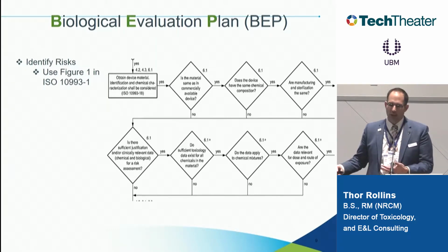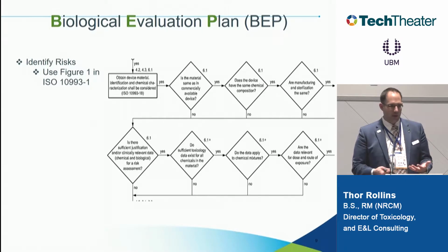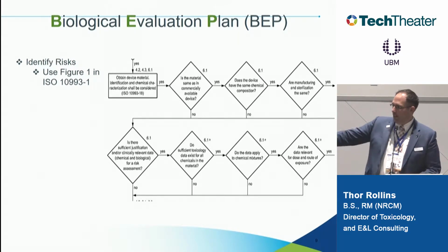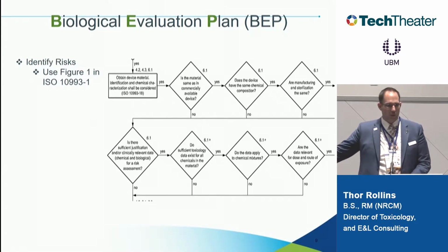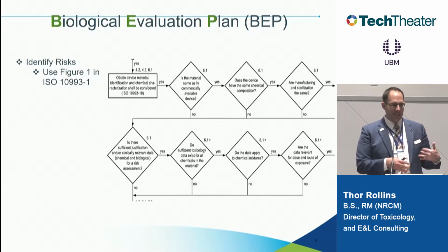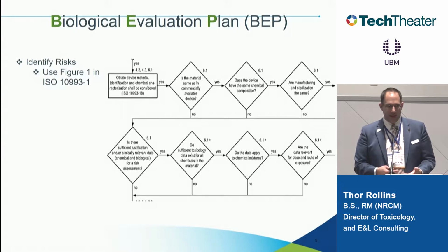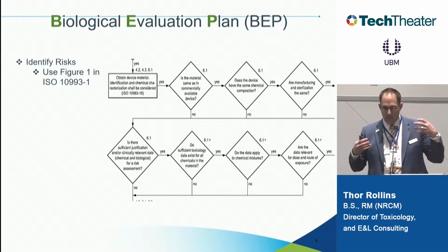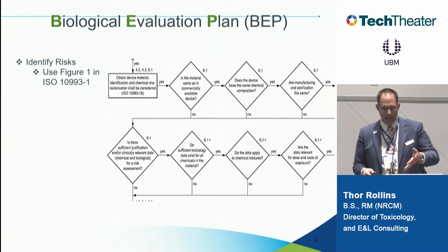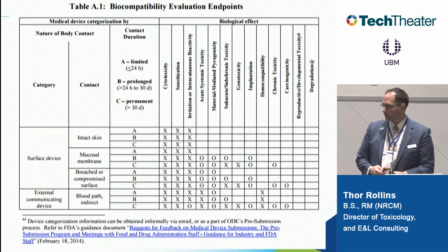It goes through questions to help you understand the risk of your device, like, is there a device on the market that has similar materials and processes, that have similar contact types? So you're able to go through this kind of initial risk-based approach to be able to understand the risk of your device and understand what testing is needed to mitigate that risk. This is that first approach that we talked about, the first steps, but it's been around forever. It's just the new -1 is trying to emphasize that type of approach.